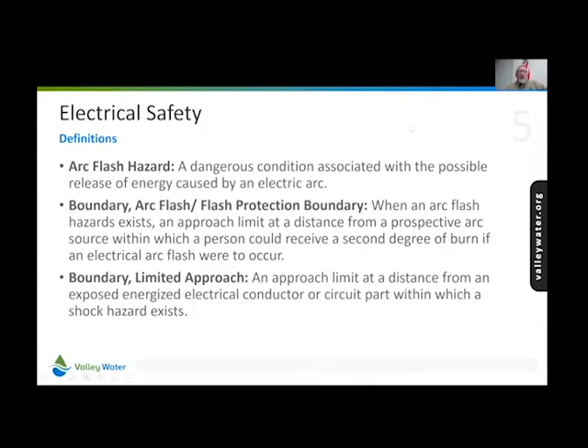Flash protection boundary, or arc flash boundary, is when an arc flash hazard exists, an approach limit at a distance from a prospective arc source within which a person could receive a second degree burn if an electrical arc flash were to occur. So that's the area that explosion can happen in.